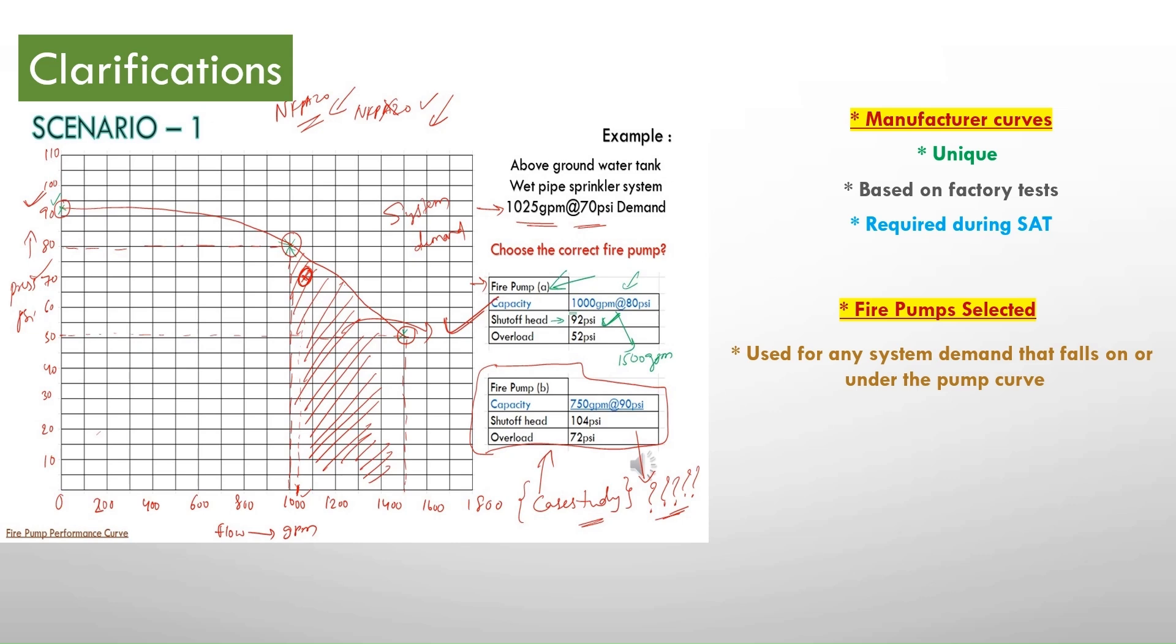It means if our system demand falls under this pump curve then we can use this particular pump. For example in scenario 1 we have 1025 GPM at 70 PSI which is under this curve so we are selecting this fire pump.